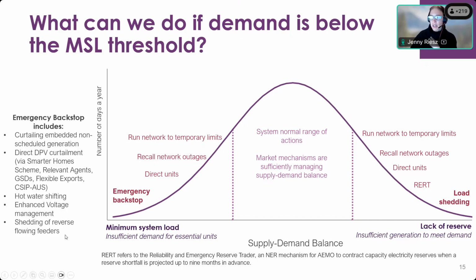The very last mechanism available to increase demand, if necessary, is to shed whole reverse-flowing feeders in the distribution network, which can effectively increase demand but has an extremely high customer impact because it sheds all the customer load on the feeder as well.